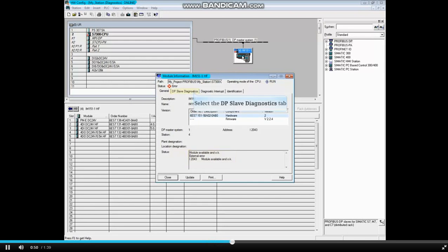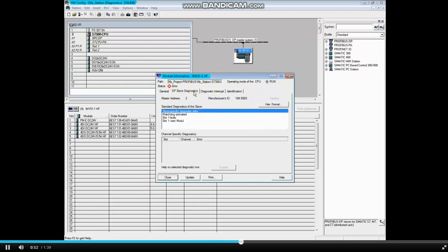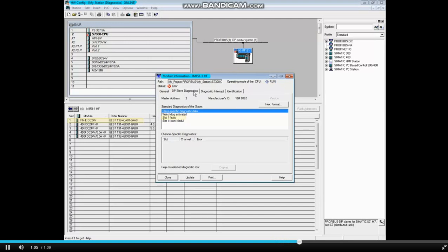Let's click on the DP Slave Diagnostics tab. Here you see that slot 1, which contains the power module, is faulty. This could be because power was lost, there is a problem with the terminal module, or a problem with the sub-module that's plugged into the terminal module.